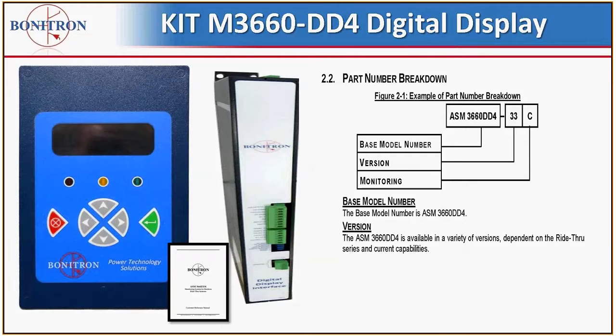This lays out, and as I said before, all this information is in the manual in one shape or form or another. And this shows the part number breakdown for the DD4 digital display. The last two numbers indicate the type of current sensors that you're going to be needing for whatever system you've got. The current sensors are rated by current, so in other words, there are going to be different versions depending on the size or rating of the ride-through. We designate this by the numbers after the dash, after the DD4. If there's a C there, that means there's a charger included in the system. If there's an X there, that means it would just be the SAG ride-throughs with no charger or external energy storage.